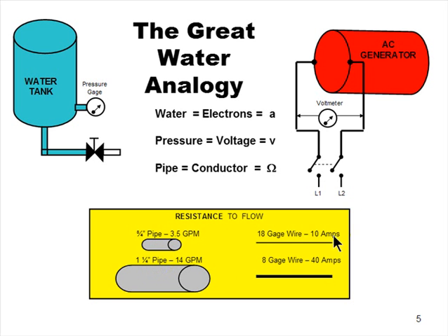NEC says you can put 10 amps, gallons per minute, amps, however you want to look at this, 10 amps, which is current, okay? Amperage is current. 6.24 times 10 to the 18th power is 1 amp, okay? 10 amps through 18 gauge wire, I wouldn't want to do that, and of course it certainly depends on the voltage. But if you want to quadruple that to 40 amps, then you need an 8 gauge wire. And as the gauge number gets smaller, the wire gets thicker. All right, it's an inverse relationship.